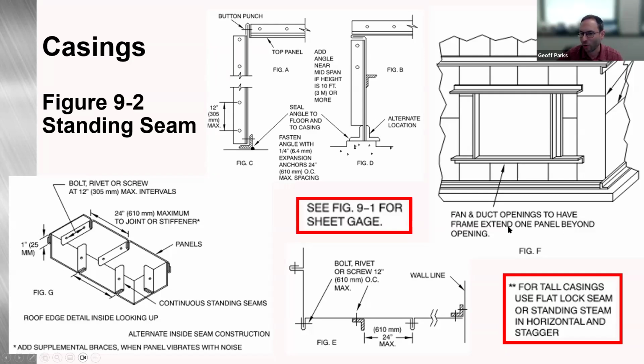It gives you some fan and duct openings that need to be framed, one panel beyond the opening. And also, if you're in the actual duct construction standard, it gives you suggested sizing for that framing as well. The sheet gauges would be per figure 9-1 that we just looked at. For tall casings, you can use a flat lock seam or standing seam in the horizontal, and you would want to stagger that. That's what we're indicating here, the staggered seams as well. And here's the spacing for your seam to your angle.